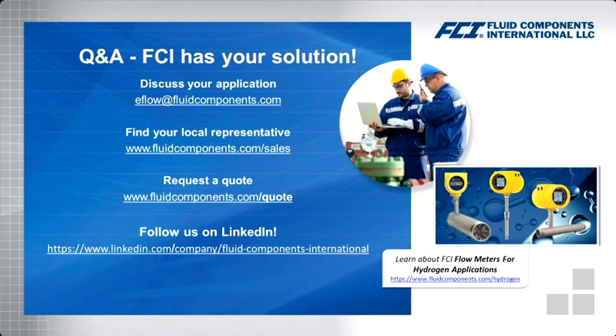What makes hydrogen so difficult to measure? Hydrogen is difficult to measure because of its physical properties. It's a very light gas. It has a very low density, and it has very low Reynolds numbers. So when you're trying to use traditional measuring meters like turbines or differential pressure devices, that low density of the gas becomes problematic. And because of those low Reynolds numbers, meters like a vortex are very limited in what they can measure, because it's very difficult in that transitional phase of the Reynolds numbers to get an accurate measurement.